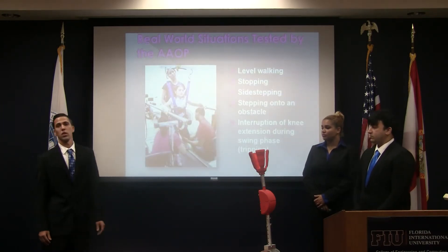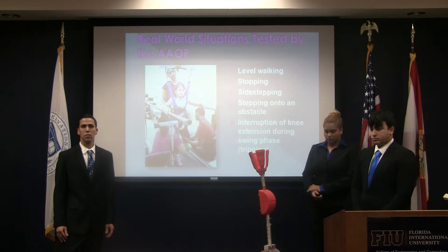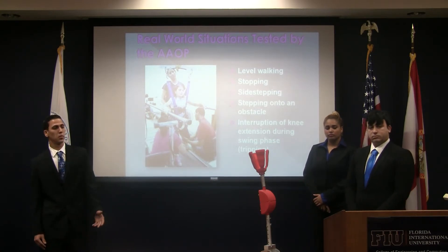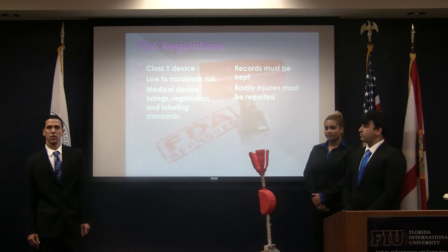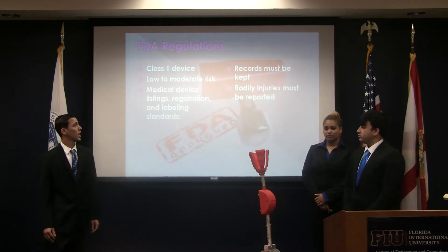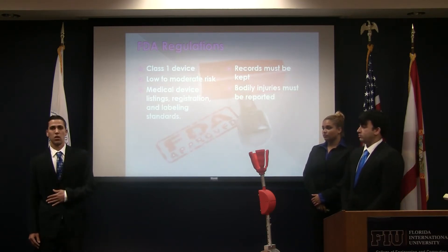This is a list of real-world situations tested by the AAOP. They test prosthetics with level walking, stopping abruptly, sidestepping abruptly, stepping onto an obstacle, and tripping the prosthetic user. The FDA classifies prosthetics as a class 1 device, which they associate with low to moderate risk. All records must be kept and bodily injuries must be reported. There's also registration and medical device listings that are important.